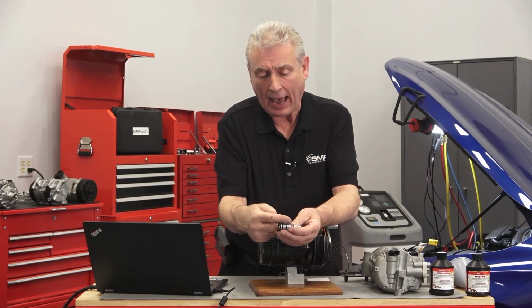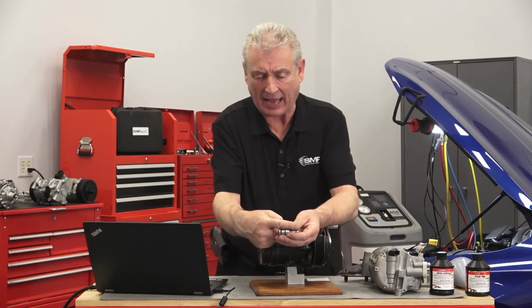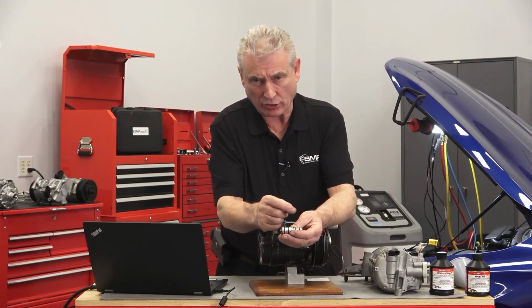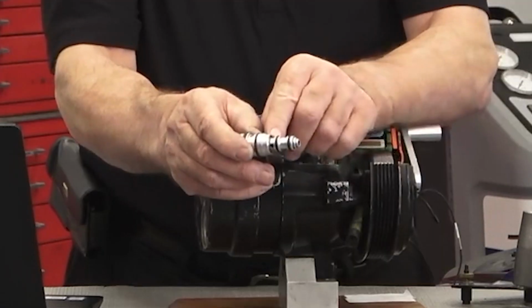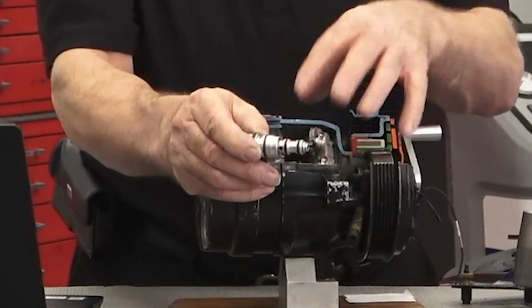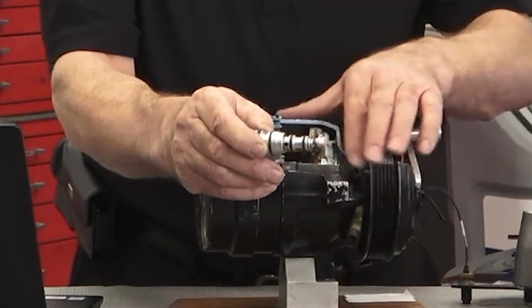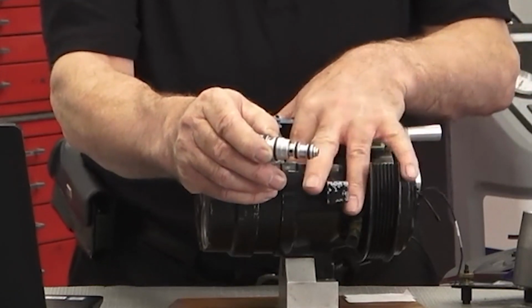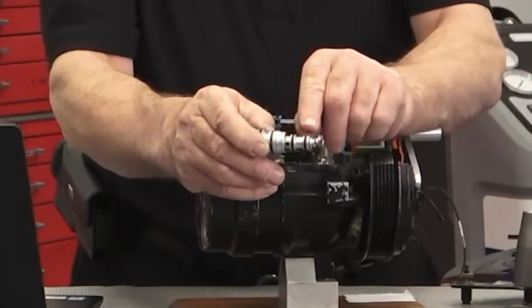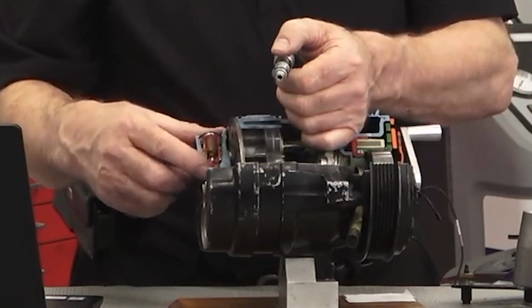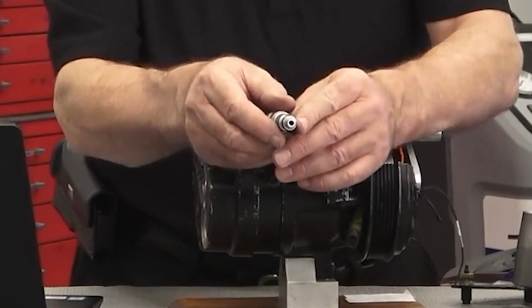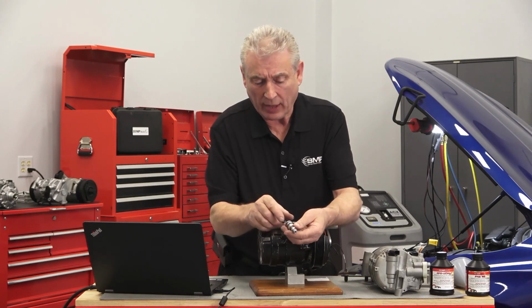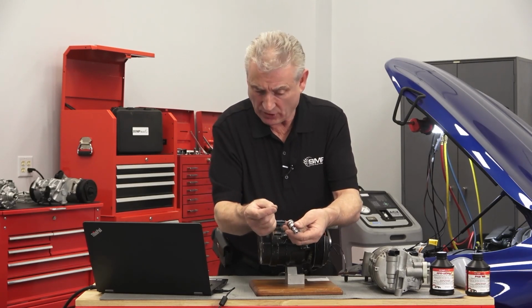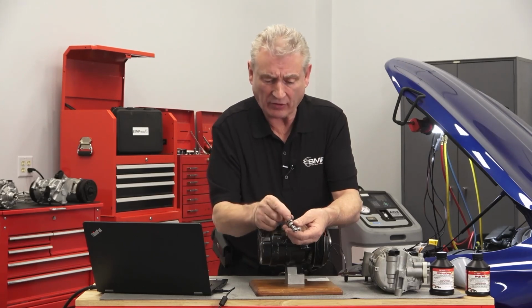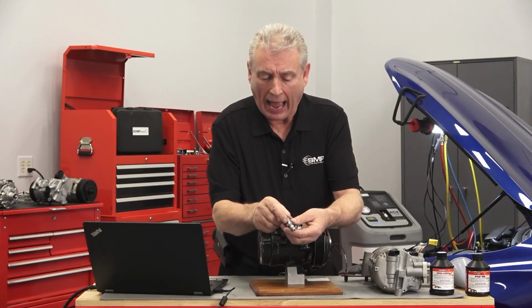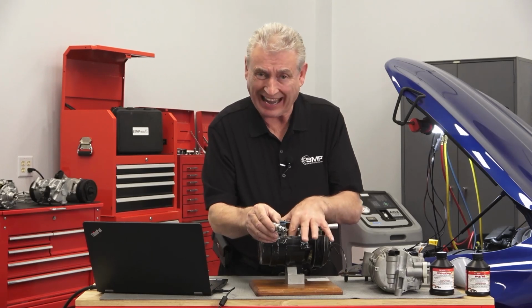and that low side pressure is going to act on the bellows inside, and it's going to move a rod inside that's going to meter the pressures into different areas of the compressor. The center section here is open to the crankcase. It's exposed to the pressure in the crankcase area of the compressor. And the very tip of it, between these two O-rings, is exposed to high side pressure. So as low side pressure changes, which is a function of the heat load on the system, I can bleed more or less pressure into the crankcase.